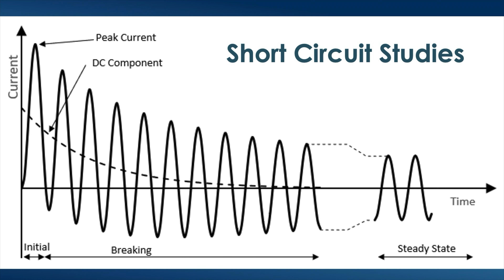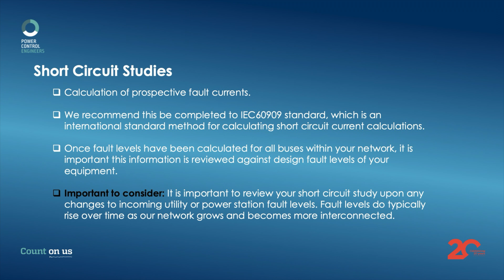So short circuit studies. Short circuit studies are the calculation of prospective fault levels. We recommend this to be done to IEC 60909 standard, which is an international standard method for calculating short circuit current calculations. Once fault levels have been calculated for all buses within your network, it's important that this information is reviewed against design fault levels of your equipment.